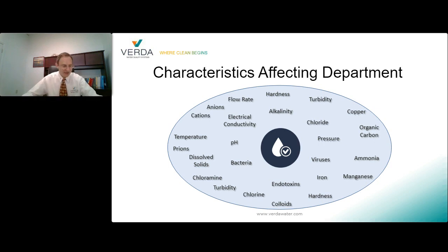Let me just go over one parameter to give you an example of what impact these things can have. Let's talk about chlorides. For utility water use, AAMI TIR 34 recommends that the chloride content in utility water be less than 250 milligrams per liter. When it comes to final rinse, it should be less than 1. Now, don't assume that your RO treated water is going to sufficiently produce water to AAMI guidelines. Right? If your water, let's say utility water, has a chloride level of 200, your RO is going to reduce 95 to 99% of the contaminants. That sounds amazing. But that also means you're going to have a chloride level somewhere between 2 and 10 milligrams per liter. That's great, right? It's impressive, but it's still too high to meet the requirements for the AAMI critical water.